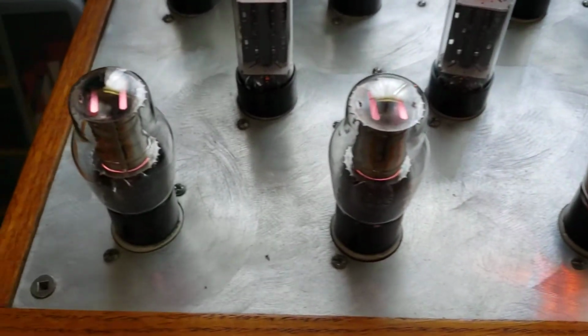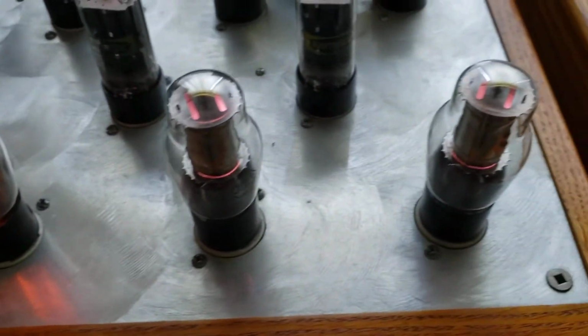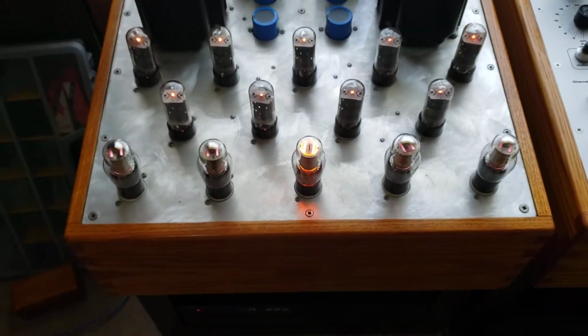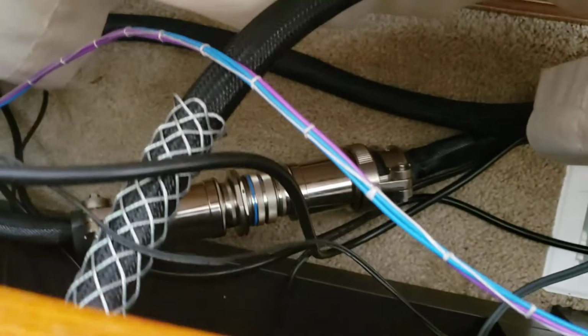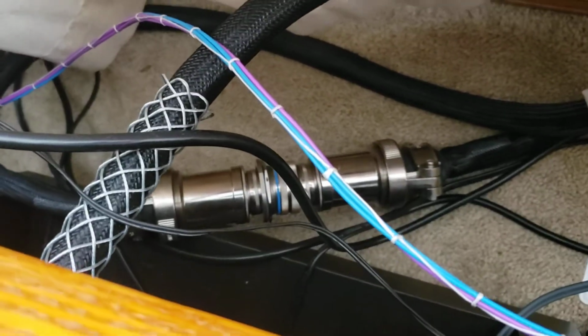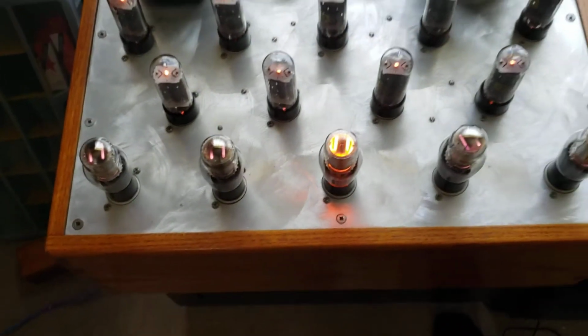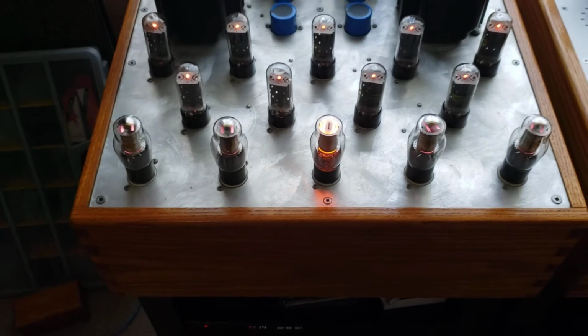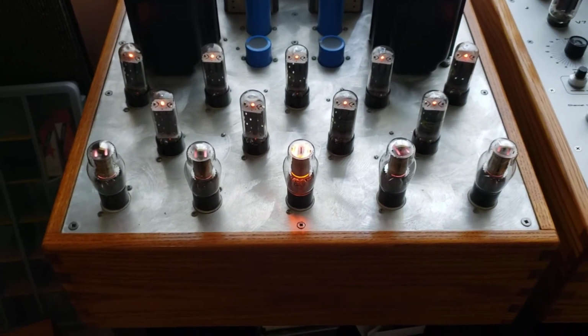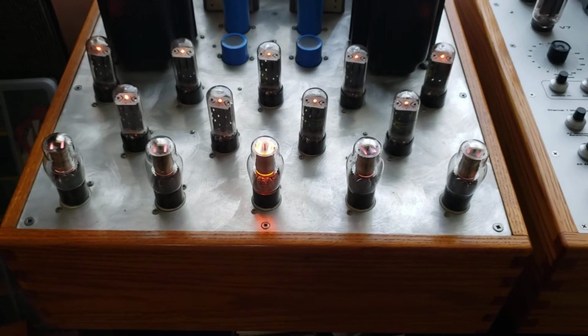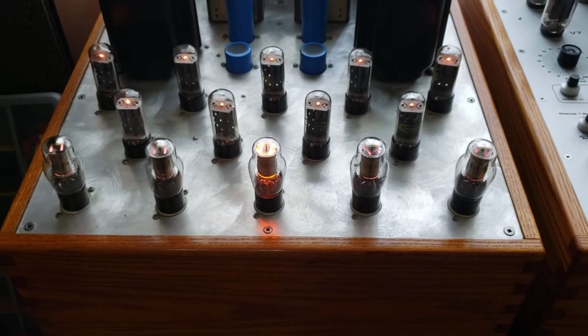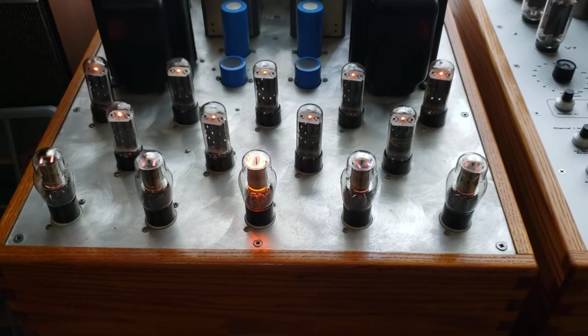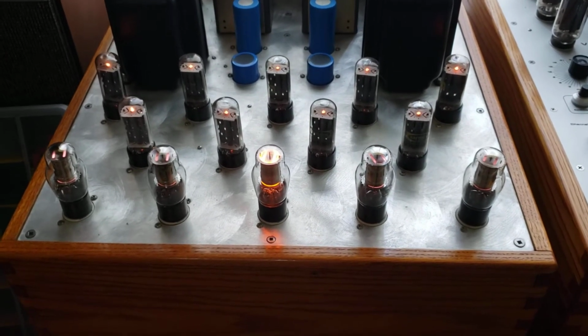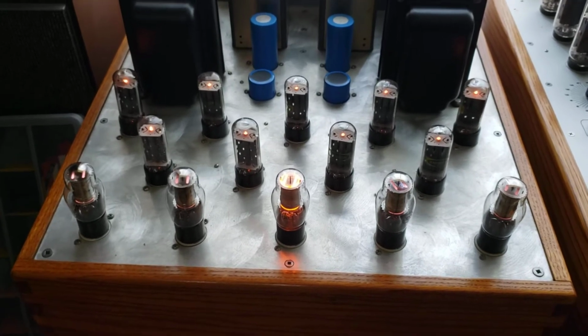Once the bias kicks in, it engages the safety circuit, which then turns on the high voltage. That has two purposes. There's a large military-spec umbilical cord connecting these two things, and if you were to unplug it, that would be bad—you wouldn't want one end sitting there with 550 volts DC on it. So the amplifier automatically shuts down the high voltage if that cord gets unplugged, and also if the bias supply fails. That keeps your tubes from melting down.